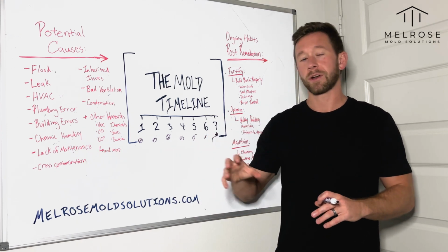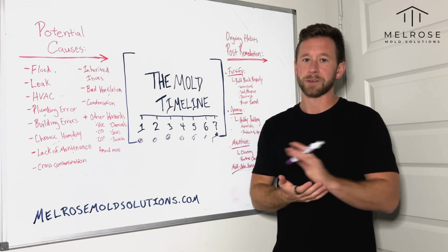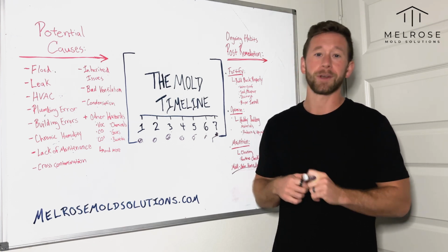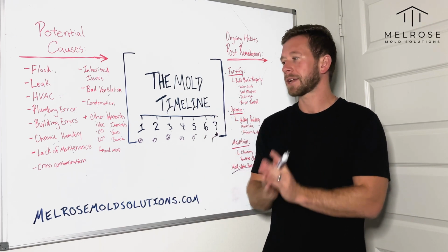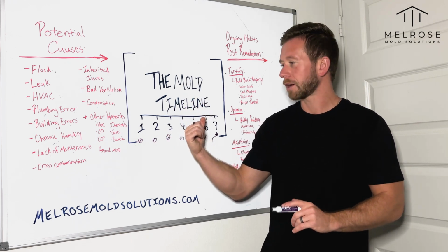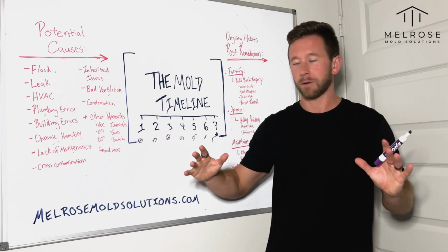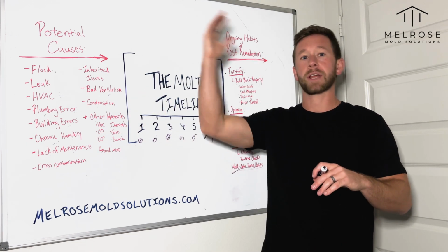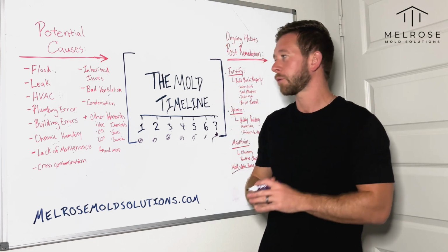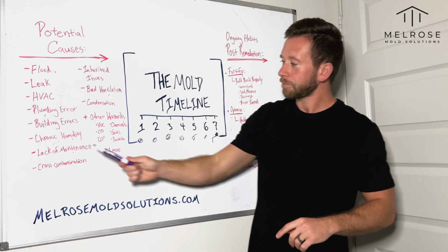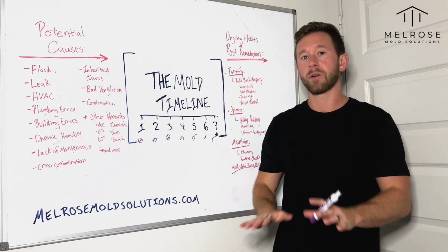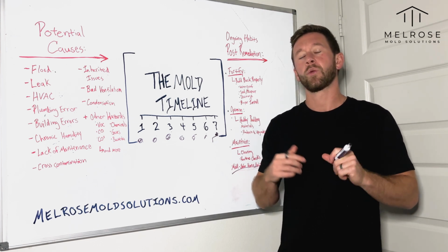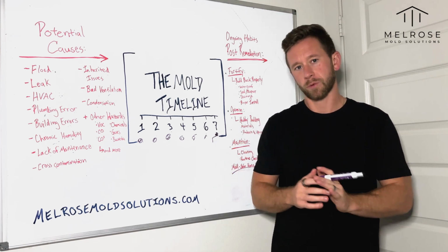Chronic humidity. So humidity over time turning chronic, that's where, again, I told you about that atmospheric issue, and I can tell stories about chronic humidity issues causing widespread mold in the house. And that's one of these things that we would never have to go through the mold timeline if we just kept humidity down, figuring out what's causing it first, of course, which could be the building, the HVAC system, the air gaps in the ceiling pulling from the attic area, and that's a common one, especially in the South. There's so many different things here, but if we can keep humidity low and keep dust levels low and keep airflow going, that's under the ventilation one here, we can control those atmospheric issues much, much more easily.